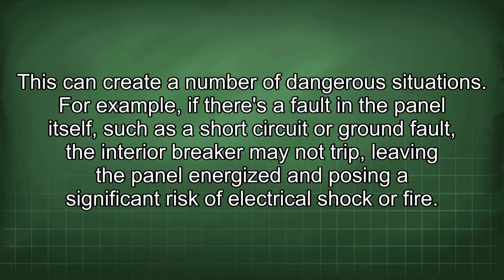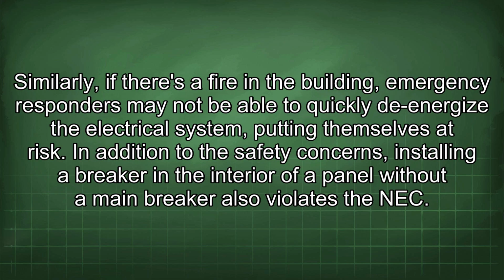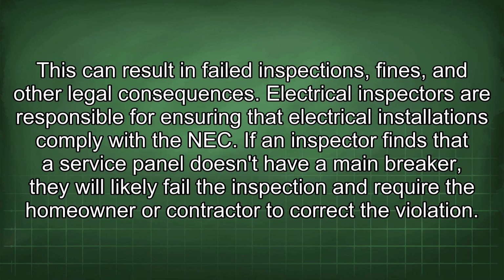For example, if there is a fault in the panel itself, such as a short circuit or ground fault, the interior breaker may not trip, leaving the panel energized and posing a significant risk of electrical shock or fire. Similarly, if there is a fire in the building, emergency responders may not be able to quickly de-energize the electrical system, putting themselves at risk. In addition to the safety concerns, installing a breaker in the interior of a panel without a main breaker also violates the NEC. This can result in failed inspections, fines, and other legal consequences.